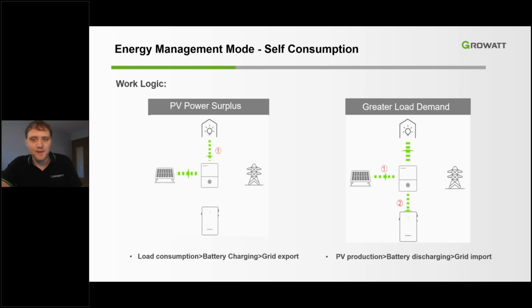So after the PTO has been granted by the utility, the inverter can now begin its normal operating procedures. Here we can see how the different work modes of the inverter are handling the exportation of energy. The maximize self-consumption mode ensures full support for the user's loads and charges the battery from clipped solar energy during peak PV array production, and allows the battery to discharge when the PV production is insufficient or not present to power the user's loads. The maximize self-consumption mode is turned on by default, so this is the normal operating procedure of the inverter. These videos show how the load consumption is prioritized.